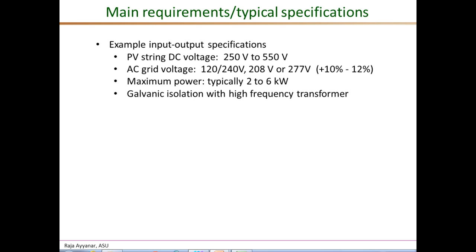As the name suggests, a string inverter operates from a single string of PV panels, and a single string can have anywhere between, say, 6 panels to about 15 panels or so. In order to be able to support these different numbers of PV panels, and also due to the fact that the PV voltage can vary significantly with temperature, the string inverters need to operate from a wide range of input voltages.